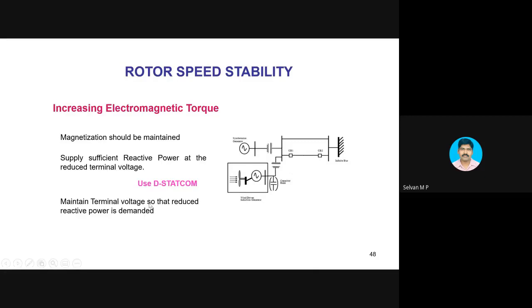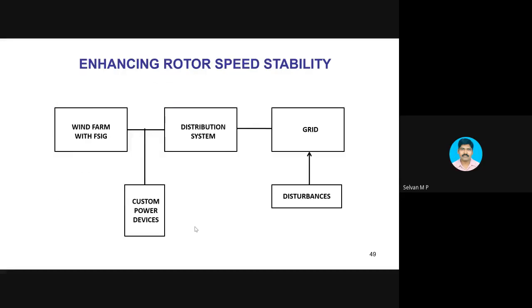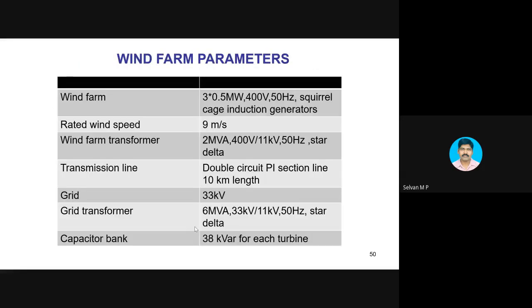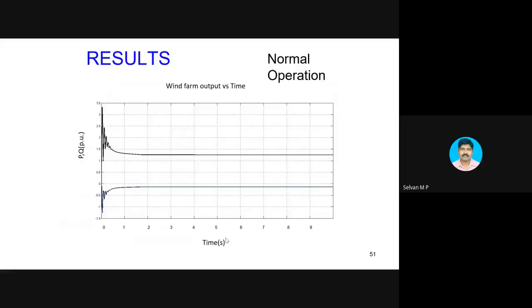So I can maintain the terminal voltage by injecting reactive power so that less reactive power is demanded by the machine, or otherwise I can use a DVR, dynamic voltage restorer, also. Now I am going to talk about only the STATCOM application. So I have considered a 1.5 megawatt wind turbine. The total output is 1.5 megawatts. These are the other details. And every wind turbine is provided with 38 kVAr of reactive power, which is required to supply the reactive power during the starting load. Other than that, it is not provided.